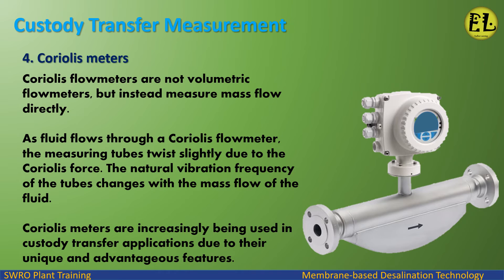Coriolis Meters: Coriolis flow meters are not volumetric flow meters, but instead measure mass flow directly. As fluid flows through a Coriolis flow meter, the measuring tubes twist slightly due to the Coriolis force. The natural vibration frequency of the tubes changes with the mass flow of the fluid. Coriolis Meters are increasingly being used in custody transfer applications due to their unique and advantageous features.